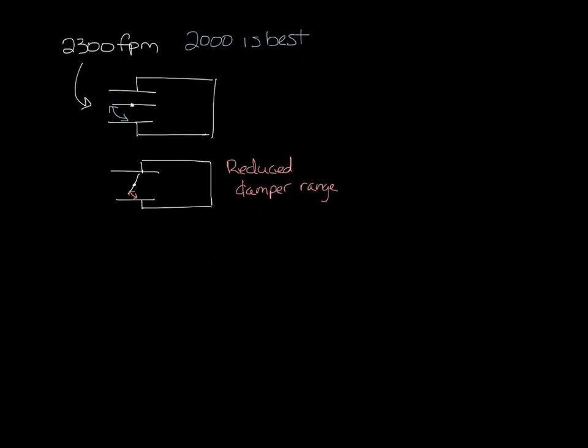So oversizing can also mean that the velocity at minimum CFM may be too low. So let's draw the inlet of the box. You have a flow sensor here, and it's piped to a controller.